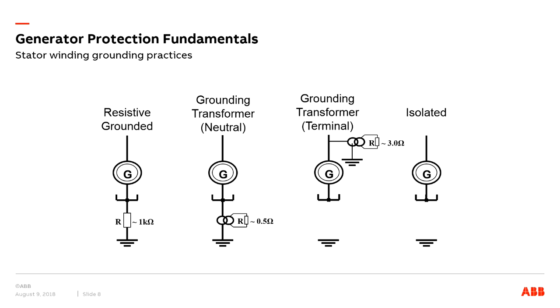And with a ground fault current, in this case, it's typically less than or equal to 10 amperes. So as you can see here, there's a resistor connected to the secondary side of the single phase transformer, and the resistor is selected so that for a single phase to ground fault at the generator terminals, the power dissipated in the resistor is equal to or greater than 3 times the total zero sequence capacitance or capacitive kVA to ground. So that's a basis on which the value of resistance is selected. Typically, it's about 0.5 ohms.